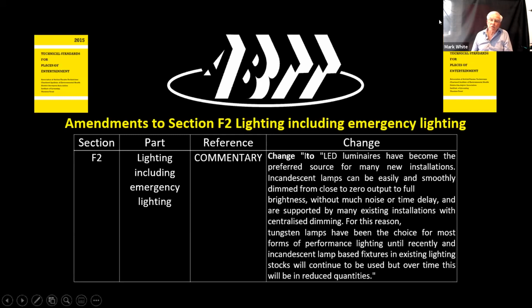Now, obviously, it's a much more complex process to test individual light fittings with individual batteries in them. So in one sense, for maintenance of escape route lighting, we still think central battery systems are better. If not, there does have to be a system in place where they're tested, and most people know that your emergency lighting system has to be tested every 3 months and a certificate produced accordingly.